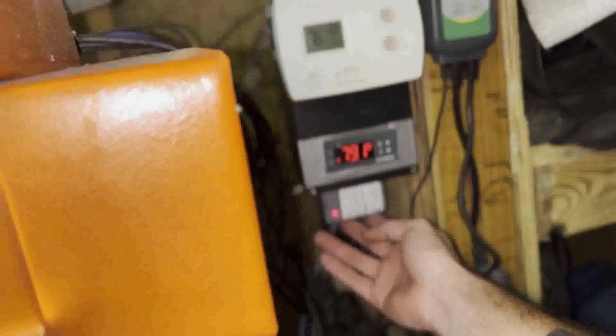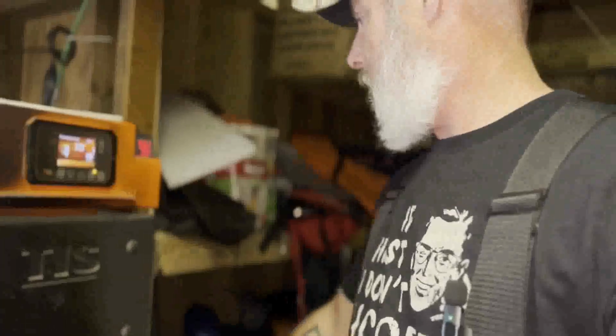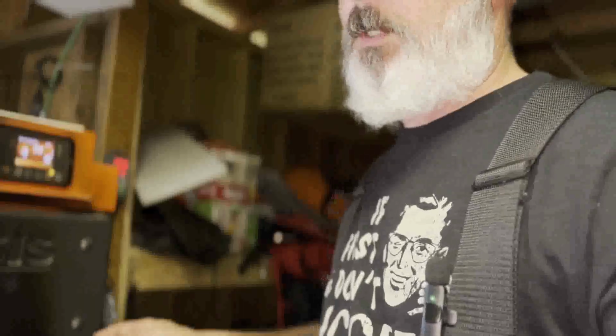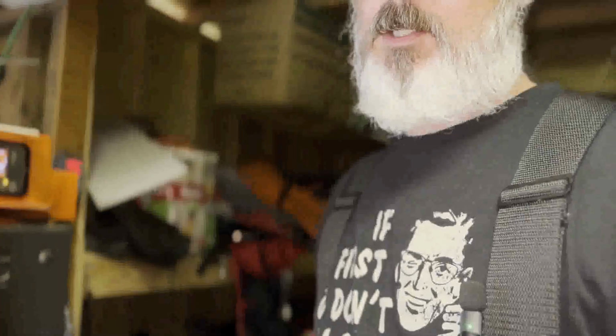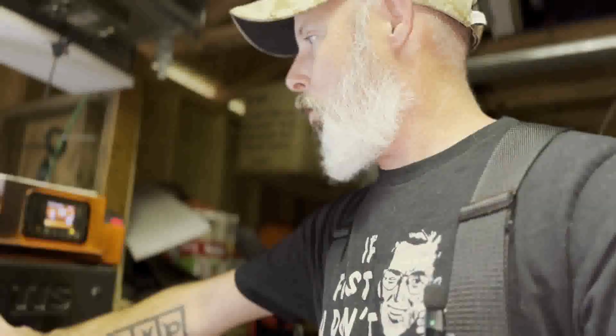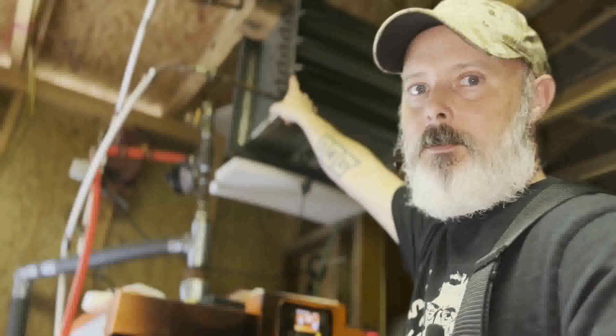But basically, this is monitoring normal power. So in the event that, let's say, the power goes out, right? Power goes out. We've had an ice storm. Power goes out. That relay is going to drop out, and when that drops out, this UPS is going to be losing power because it's seeing the same ultimately 120 that this relay is seeing, and when that 120 goes away, the UPS kicks in and makes 120. So what happens is at that point, because there's going to be a fire in here, and fire just doesn't want to shut off. It's a low mass boiler, and I don't want this thing to overheat. So this is now a dump zone up here.